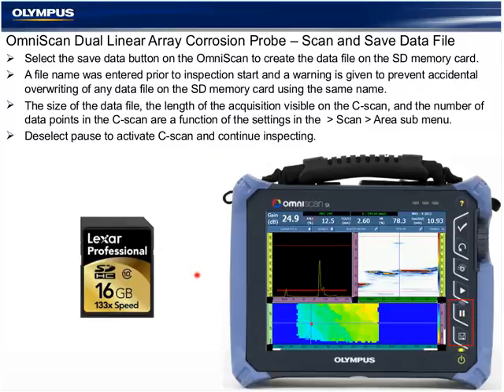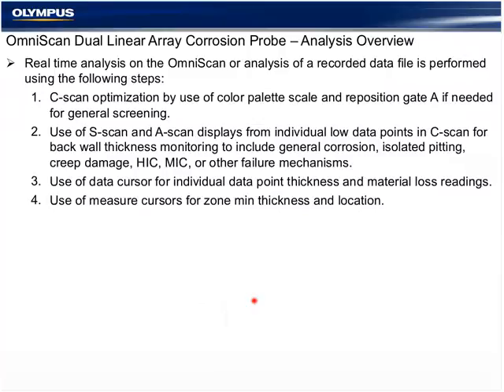So when you're either on a clock inspection and you've acquired a piece of data, or you're on an encoded inspection and you've taken the entire C-scan depth or length, select pause and save data, and the data is on the flash card. It can be analyzed either directly on the instrument, offline using OmniPC, or converted to TomoView for more options for the C-scan and the C-scan export.